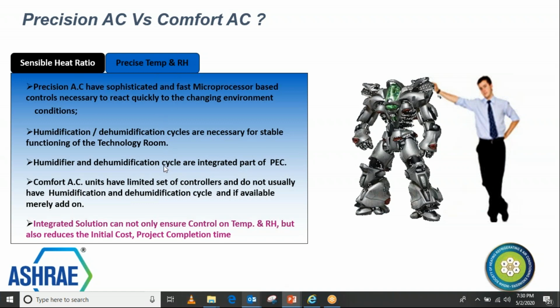And imagine that you have lower humidity in the room. What happens in the lower humidity case? When your humidity is low, you are going to end up having problems of electrostatic failures. Most of the time we see that the air becomes highly dry in low humidity. When the air is dry and the component is continuously operating, there is a chance of electrostatic issues. In many places we see these kinds of problems. That's why the range of lower and higher humidity is defined for all critical environments.